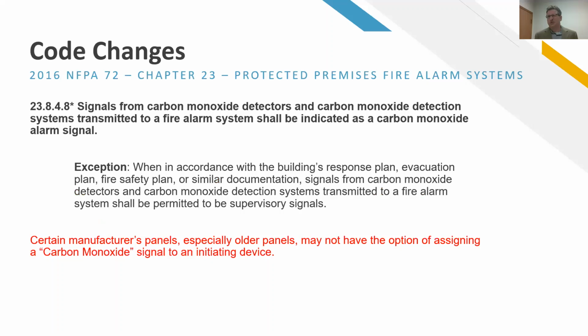So this section is in regards to carbon monoxide. Again, if we have carbon monoxide detectors in our building, we have to send a carbon monoxide signal to our central station. Just be careful. Some older fire panels don't have the ability to do this. So you might end up in a sticky situation sometimes where you have an ancient panel that can't send that carbon monoxide signal. So just something to be aware of. And all modern systems that are addressable, intelligent should be able to differentiate that signal via zone to the central station.